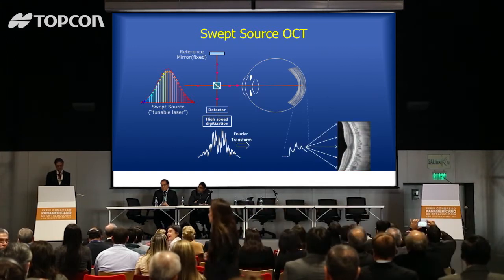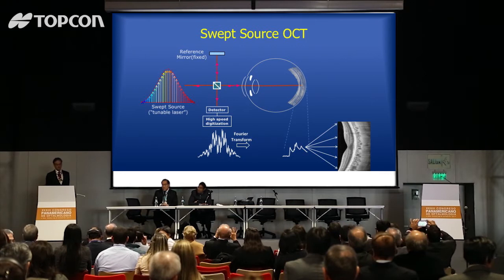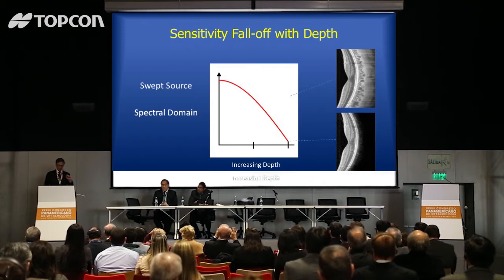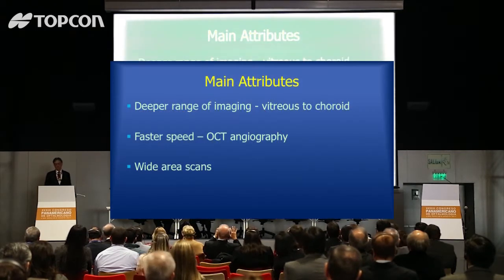With spectral domain OCT there was a fall-off in sensitivity so that deeper structures weren't seen well. With swept source, there's almost no fall-off. So we get a much better image through the full depth of the eye — we can see from the vitreous to the choroid without selecting any one of those things. We get them all at once. The OCT also works at a much higher speed because we don't need to wait for a line CCD to charge up.